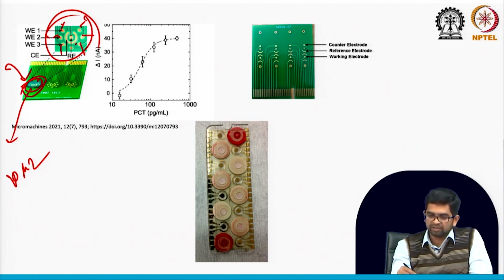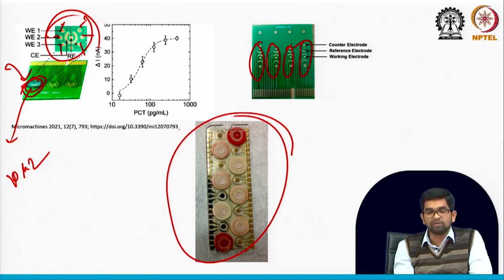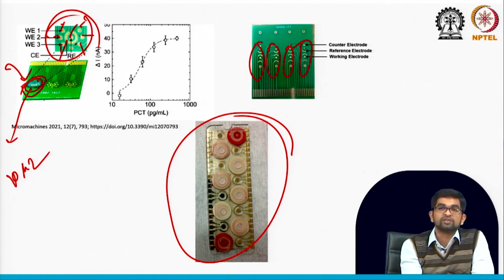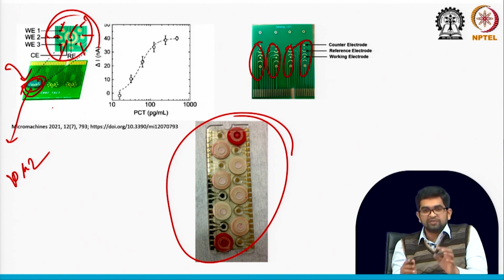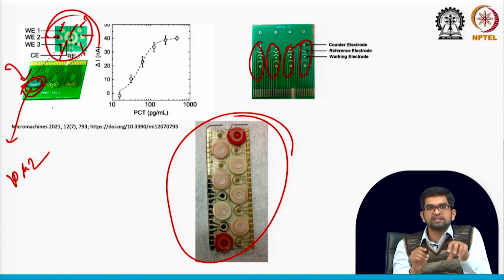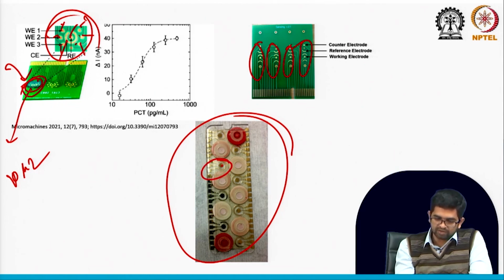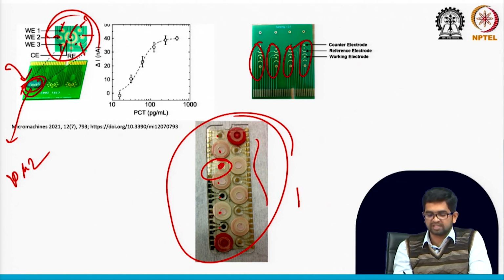Again, this one I taught you. See here 1, 2, 3, 4. So 4 targets you can detect at the same time. Another one is commercially available, a gold chip. Here we are sharing the counter electrode and reference electrode. Sometimes, if you feel that you want to use an independent reference and counter electrode for each working electrode, see here, this is the design: one working, one reference, one counter. See 1, 2, 3, 4, 5, 6, 7, 8, and the opposite side also. So 16 targets we can detect at the same time.